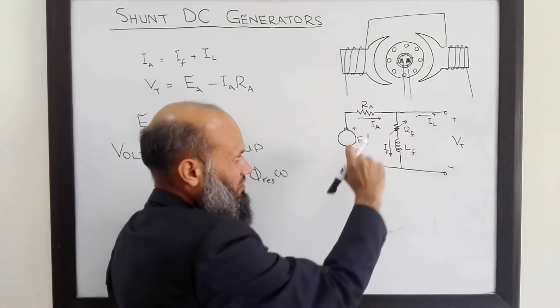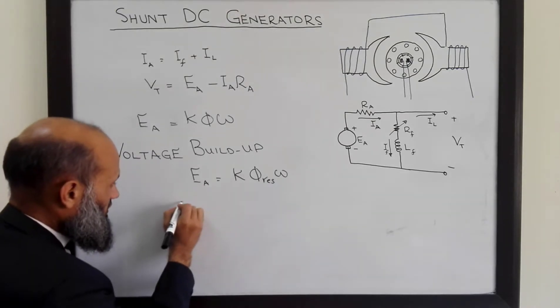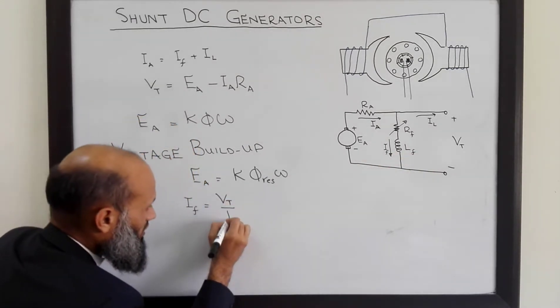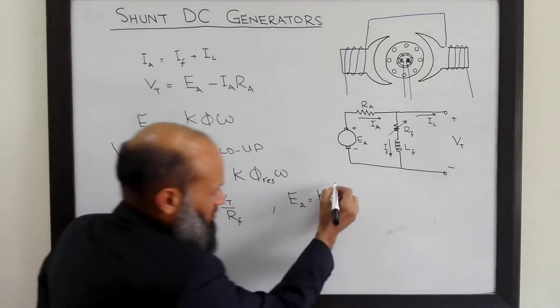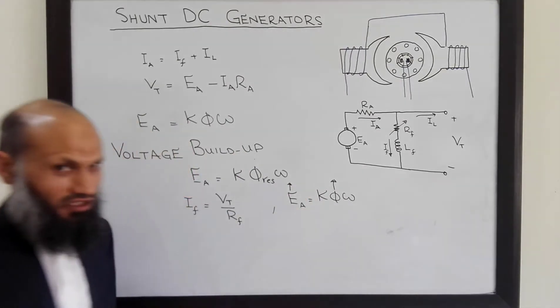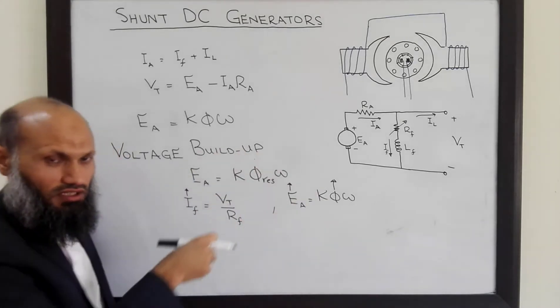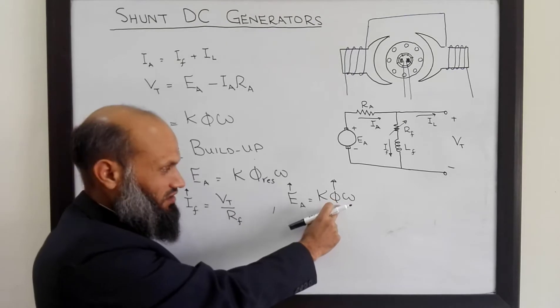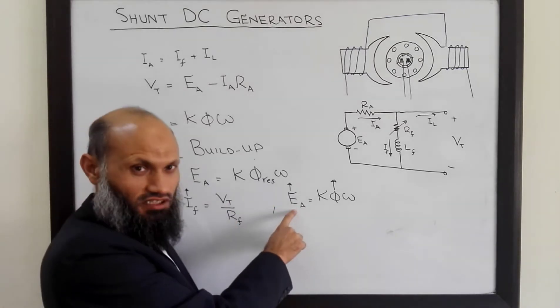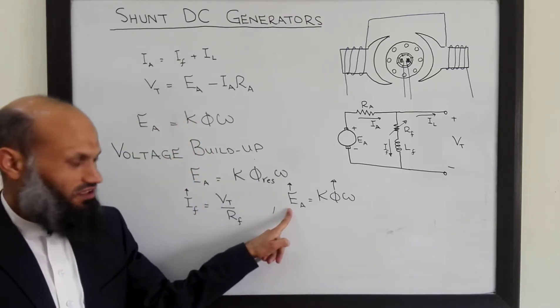Although there is no field current initially, there is some small residual flux in the poles of the generator. Due to this residual flux, a small voltage is generated. This small voltage results in some field current, since field current equals terminal voltage divided by field resistance. Due to the flow of field current, flux in the machine increases, which results in an increase in the generated voltage, which in turn results in further increase in field current — and this cycle continues.